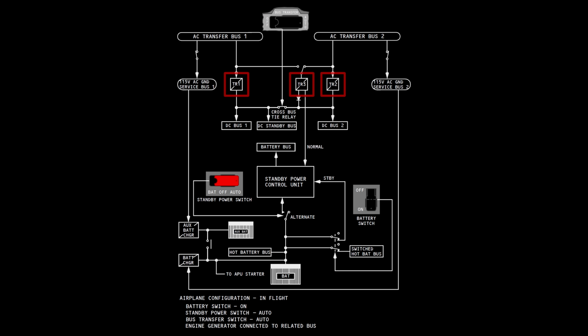DC power is supplied by 3 transformer rectifier units, or TRs, which are energized from the AC transfer buses. TR1 and TR2 receive power from the respective transfer bus. TR3 normally receives power from transfer bus 2, with transfer bus 1 a backup source of AC power. Any 2 TRs are capable of supplying the total load.